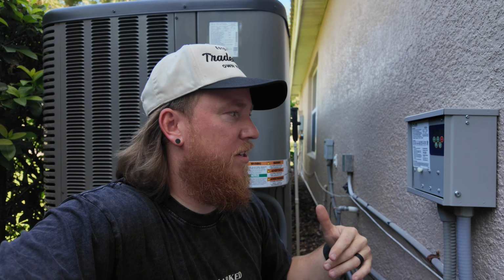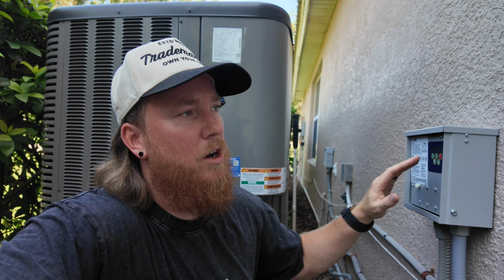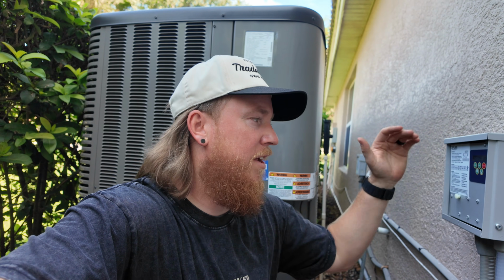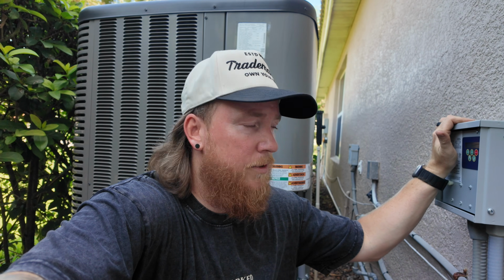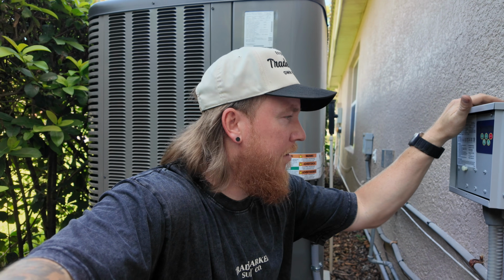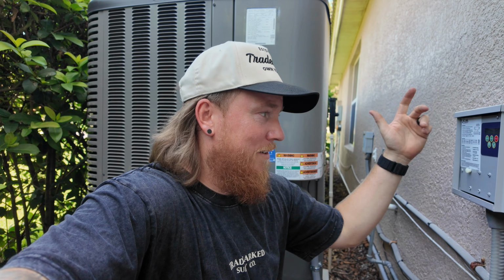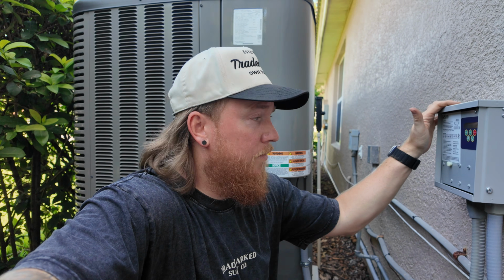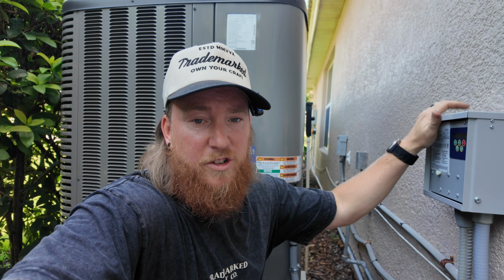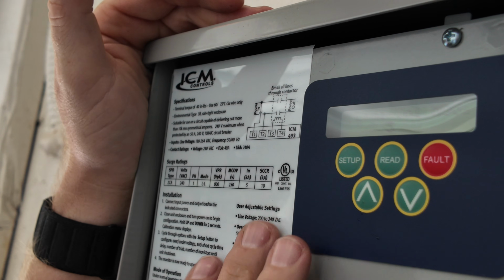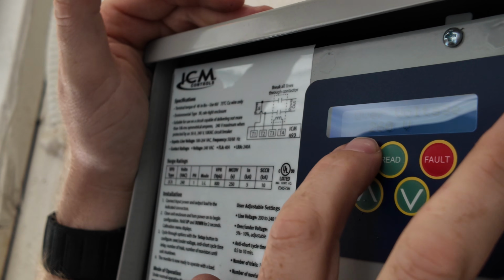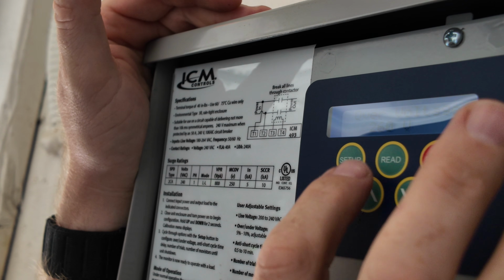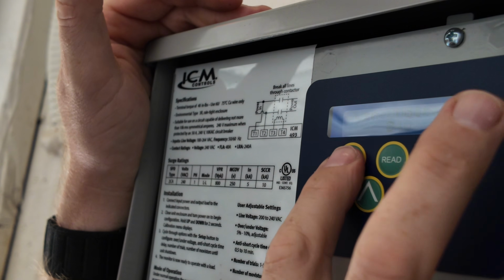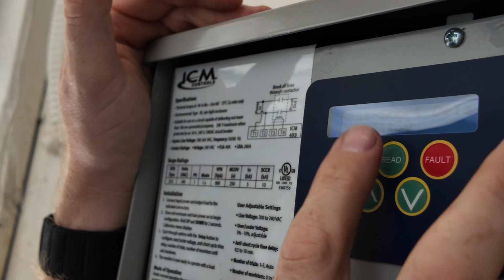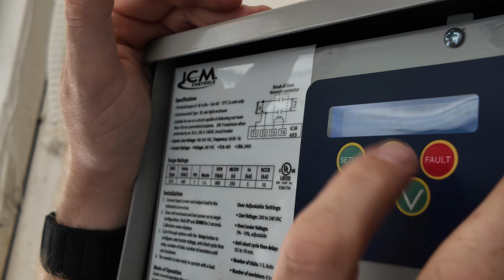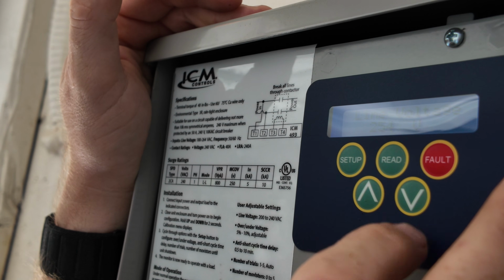And what you can do with that is you can set it to 4, and if you set it to 4, it'll be a hard lockout. It'll let us know there's only 1 left, and the customer can contact us for a replacement of one of these. But that's the issue they're facing here. I mean, it's a voltage issue, and quite frankly, this is doing what it's supposed to do. This is the one I put on the indoor unit, so I wanted to go ahead and check. See, we have that 260 over voltage here, and we have this at the 240, 8%, 90-second reset with the auto, and 5 MOVs. So we'll go ahead and read.